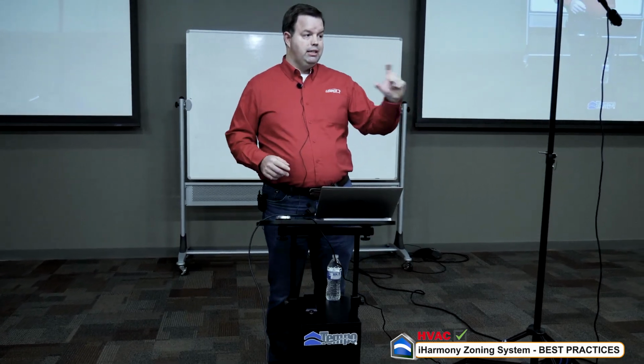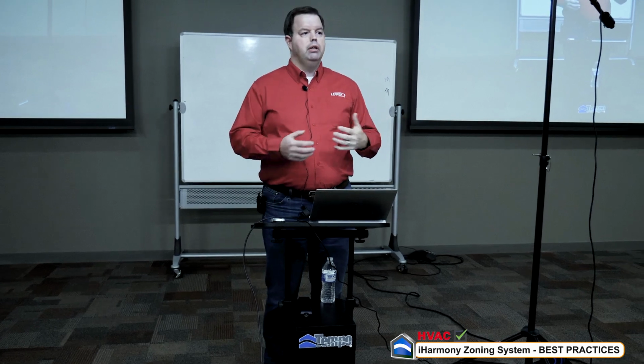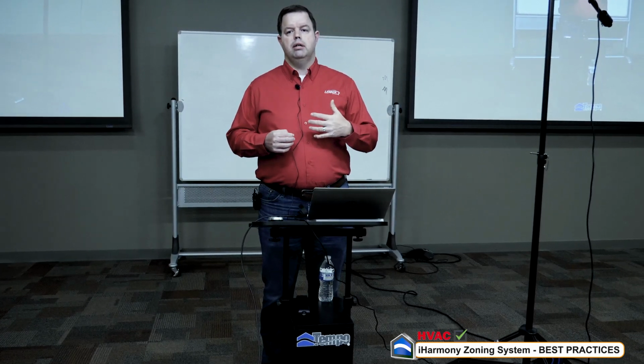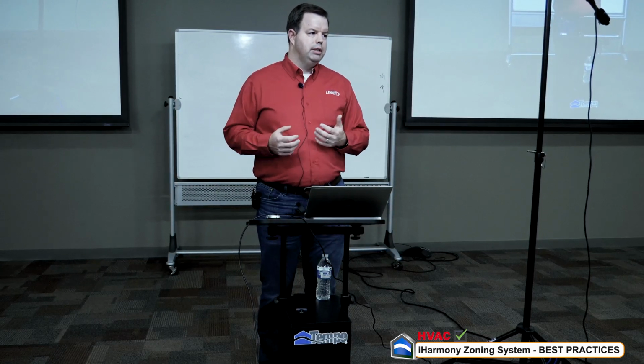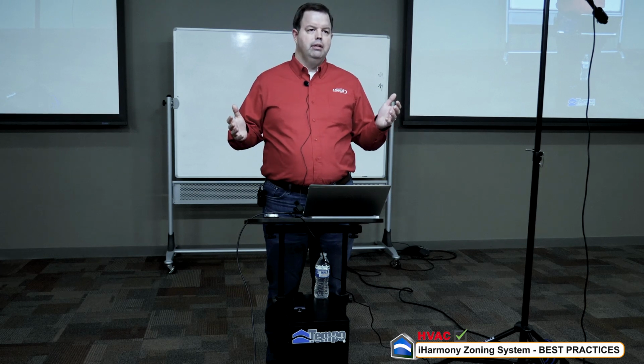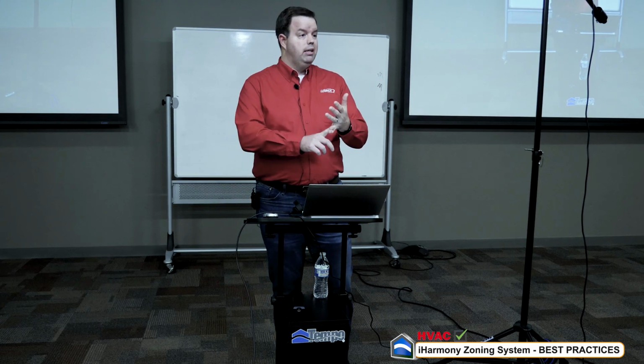So that diagnostic screen also for the zone board will let you look at the discharge air temperature. That can be another indication where if the discharge air temperature is high in cooling or low in heating, that can be an indication that we're running way too much airflow. So indoor blower power is kind of a poor man's static reading. So if that's high, then we need to reduce that CFM, or we need to rework our ductwork. Or we've got a damper stuck closed, something miswired, something like that. But that's an indication there that our blower's working too hard and we're gonna have problems down the road with it. I have a question.